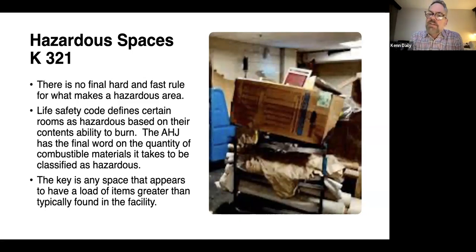in every building, there's an expected load of combustible material. So there's how much is expected from the bed, the overbed table, dresser, or maybe a desk and a chair in an office, whatever. There's an expected load. A hazardous room or a hazardous space is where the load of combustible material is greater than the expected. This is where you end up having a space that requires the door to be kept shut and latched at all times. That's why you have an automatic closer. Sometimes you use spring-loaded hinges. Either way, it's fine. But the door remains closed, and if I pass through that door, it closes behind me.